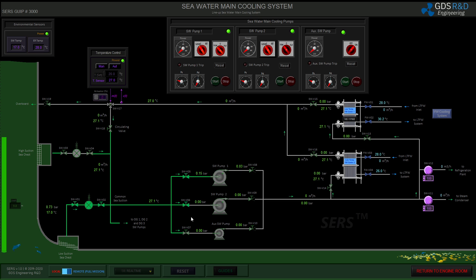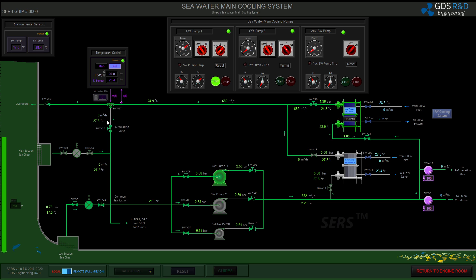I will start the sea water cooling system with the main sea water pumps, using cooler number one. I'm going to start the sea water pump in automatic mode and use sea water pump number two as backup. Line pressures are being stabilized. I'm going to switch the temperature controller to auto position so it will circulate.